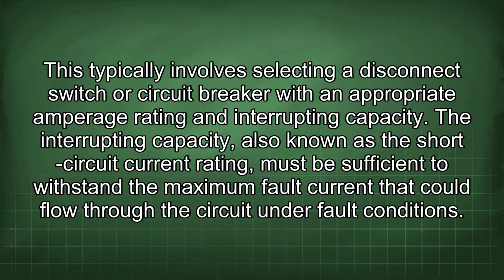This typically involves selecting a disconnect switch or circuit breaker with an appropriate amperage rating and interrupting capacity. The interrupting capacity, also known as the short circuit current rating, must be sufficient to withstand the maximum fault current that could flow through the circuit under fault conditions.